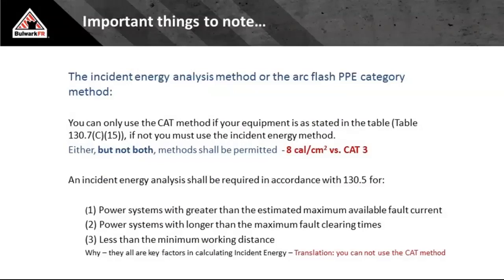So this slide is telling you that whether you use the incident energy analysis method or the PPE category method, they have their pros and cons. There are a lot of caveats in the 70E standard where you don't have an option. For example, if you have power systems with greater than the estimated maximum available fault, maximum fault clearing times, or less than minimum working distance because you have to be closer than what has been calculated, you can't use the CAT method. You have to default to the incident energy method, and it doesn't leave you any options.